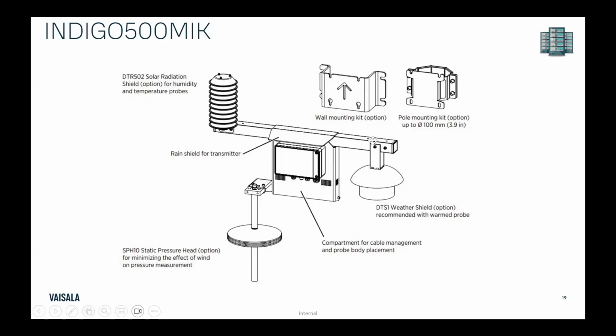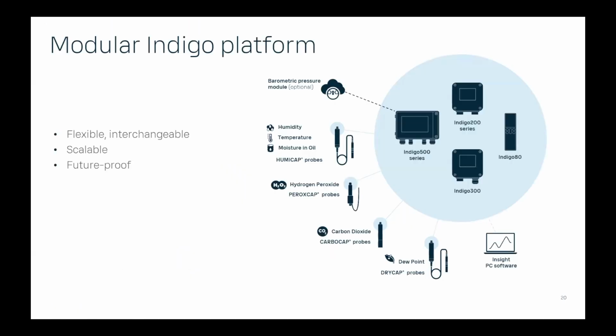And then here on the bottom, we have our SPH20, or SPH10 in this case. This is a static pressure head. What this does is it mitigates any wind noise or wind interference and allows you to get a stable barometric pressure measurement.